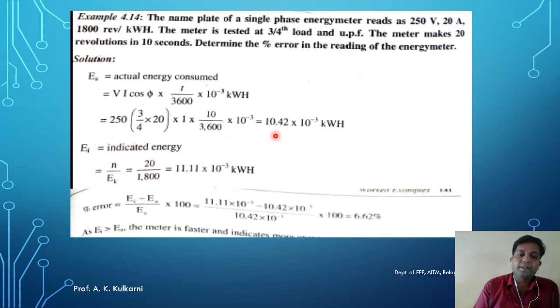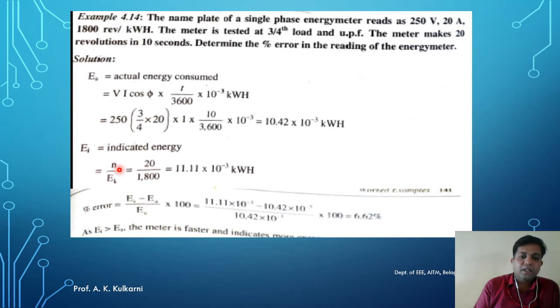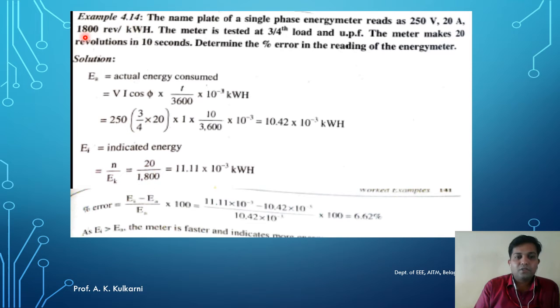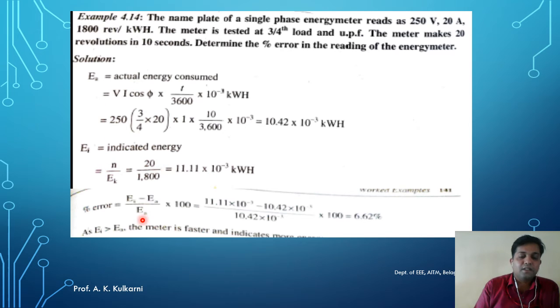Now let us find the indicated energy. The indicated energy equals the number of revolutions divided by the energy meter constant. The meter makes 20 revolutions, and the energy meter constant is 1800 revolutions per kilowatt hour. So indicated energy = 20/1800 kilowatt hours. After substituting in the percentage error formula, the error comes out to approximately 6.62%.